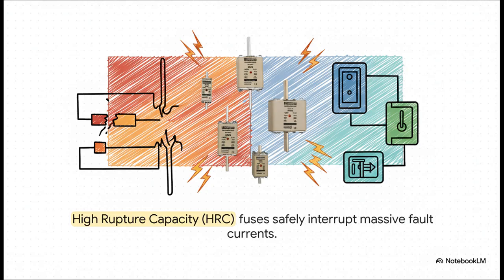And this right here is a perfect example of how specialized and serious fuses can get. These are called high rupture capacity, or HRC, fuses. They are absolute beasts. A lot of them are actually filled with a special kind of sand to absorb the energy and extinguish the electrical arc when they blow. You'll find these in massive industrial settings, protecting grids where a fault can mean hundreds of thousands of amps, a situation where failure is just not an option.